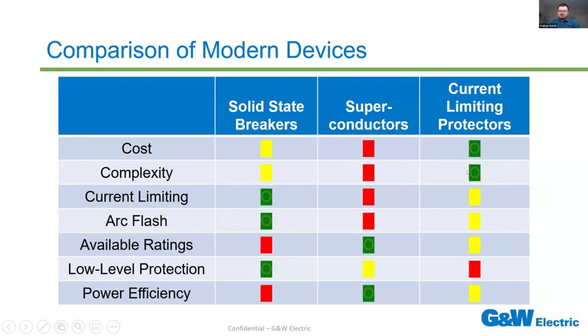In terms of complexity, once again, there's not much to say. There's only one setting with the current limiting protectors. It does require power, but there's no additional cryogenics or additional settings that you need to worry about. Now, in terms of current limiting and arc flash reduction, solid state breakers are obviously going to be your best choice, as they're going to be able to completely eliminate that fault in microseconds, which is pretty much as fast as you could possibly go. That's going to virtually eliminate any arc flash current limiting risk.